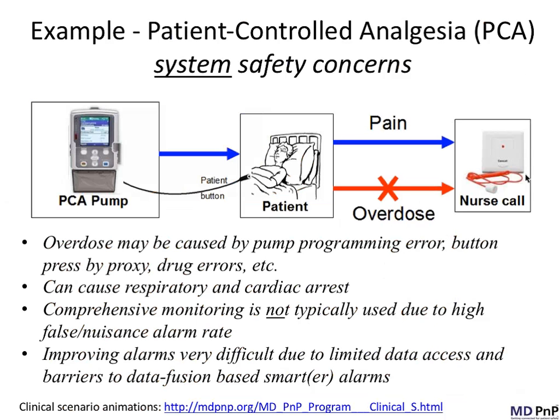As an example use case, consider patient-controlled analgesia, or PCA. Up to six people per day in the U.S. are either seriously injured or killed as a result of mishaps with PCA. The PCA is used to administer a powerful opioid like morphine, which will depress respiration and lead to cardiac arrest if there's an overdose. The patient presses the button to receive a dose, and someone else may press the button for the patient — that's called PCA by proxy — or there could be a drug dosing error. We don't nationally monitor all these patients comprehensively because of the high false alarm rate.